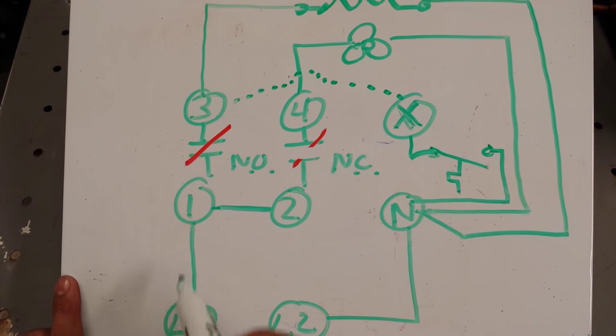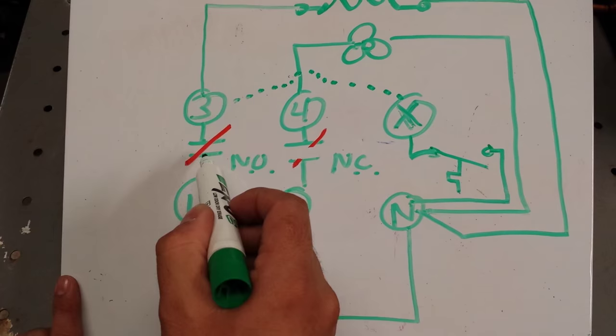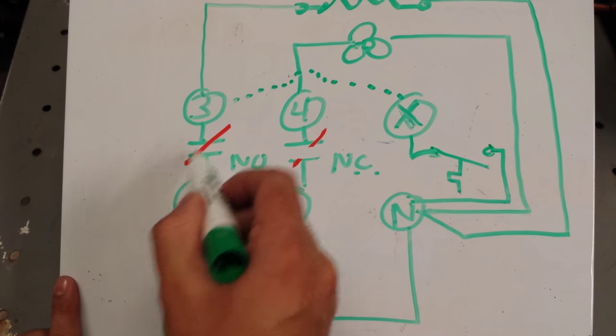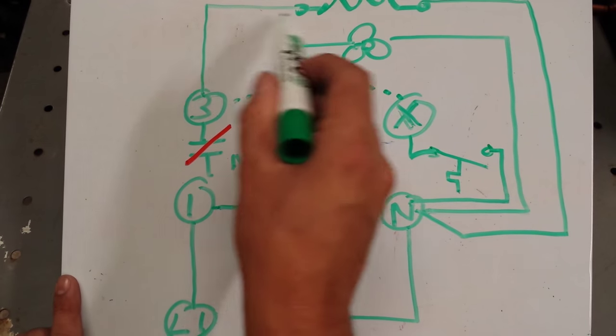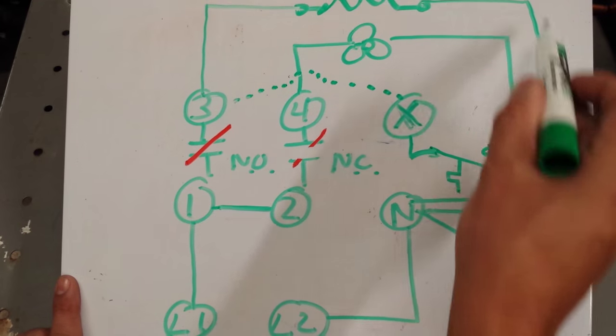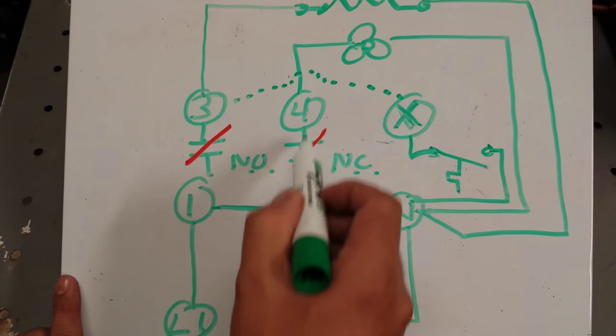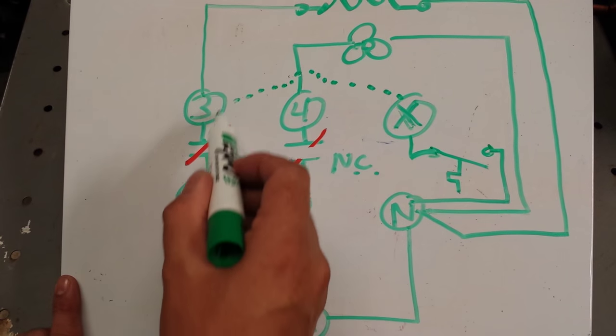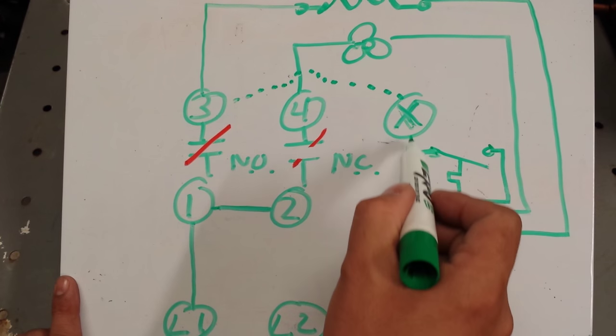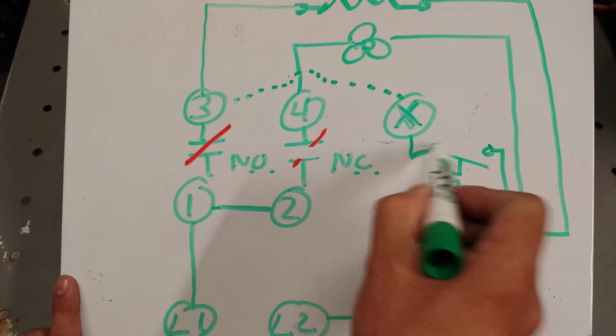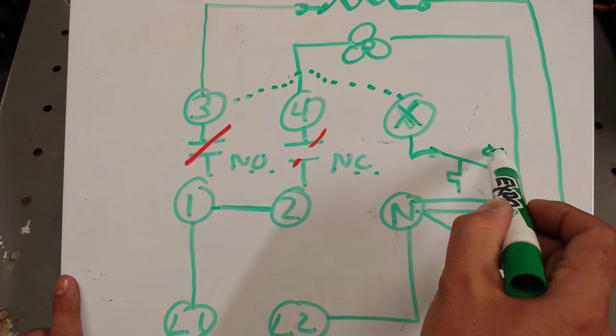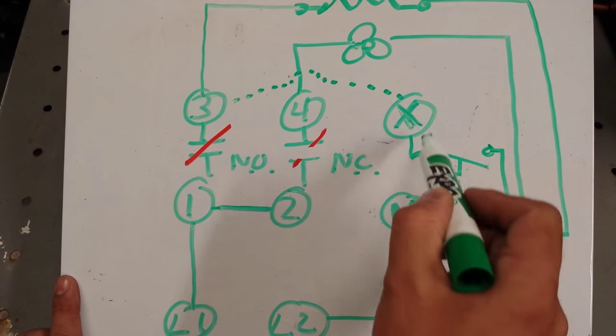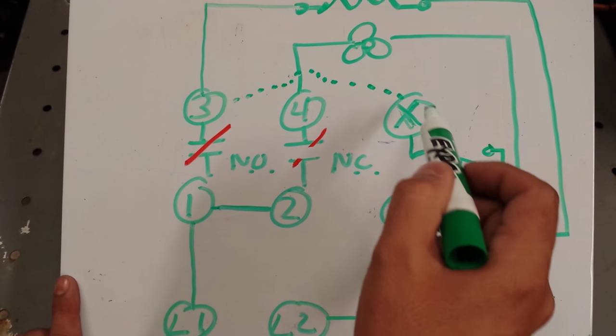Alright, so what that means is right now, the way our circuit is now, it's in defrost. This contact point is closed, defrost heaters are energized, complete the circuit there. This circuit is open, fans are off. L1 is also being supplied here in the background, terminal X, which feeds that L1 to the thermostat here. When this thermostat closes, it's going to complete a circuit.